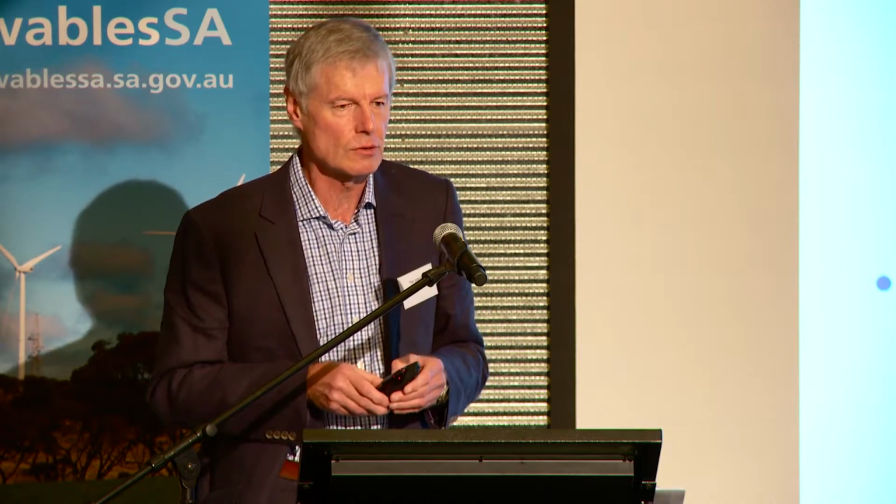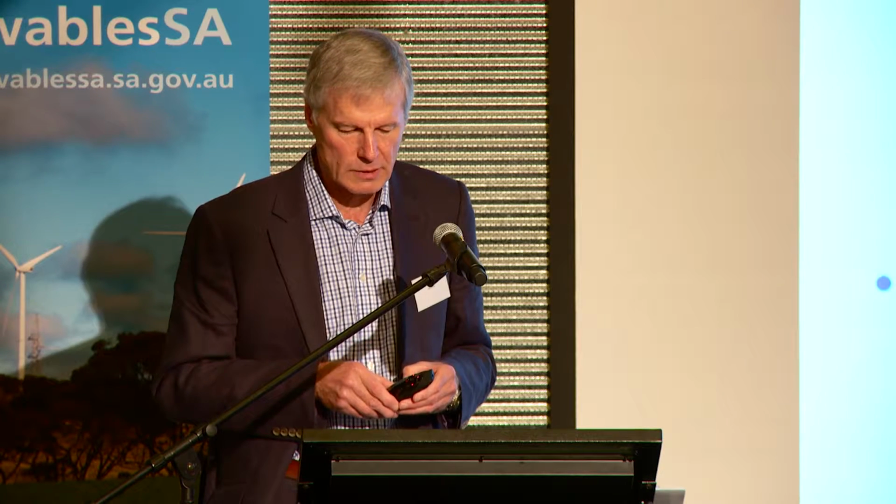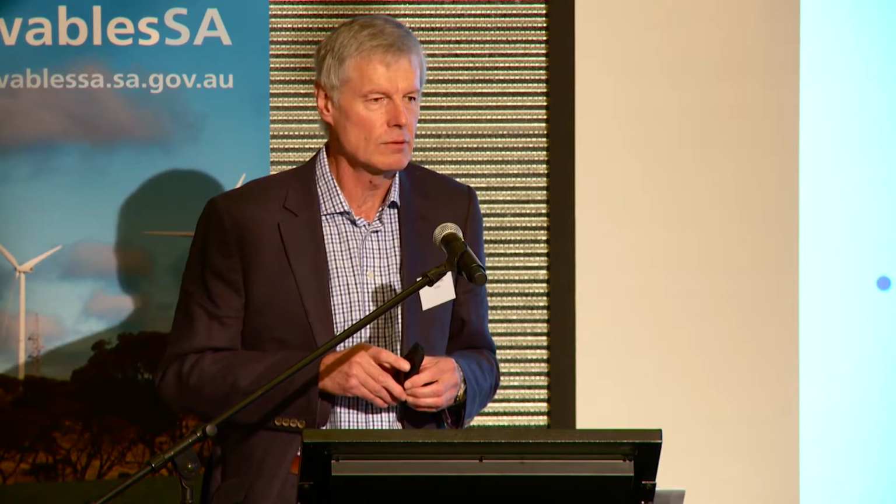Now, at the smaller scale, you tend not to get the ability to have very high steam conditions, and so you can burn the fuel rather more cheaply at a lower temperature. Instead of using steam as a working fluid to produce electricity, you can use an organic fluid, and that's normally called an ORC, or an organic Rankine cycle, which means you can use lower quality heat and still convert that into electricity. This has become popular also for geothermal power stations. If you don't get high quality geothermal steam or geothermal hot water, you can use an organic cycle.